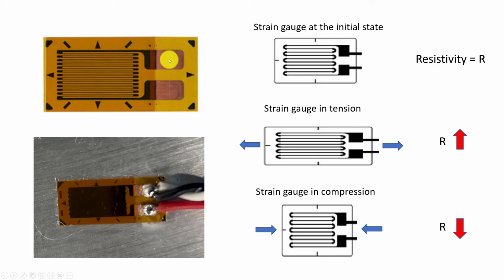Is there a polarity issue with the white and the black and the red wires? Well, we have no polarity issues with the strain gauge. It doesn't matter if I had soldered the red wire here or here, or put these two wires down here. There's no polarity, positive, negative issues like a battery being installed wrong into your remote control.